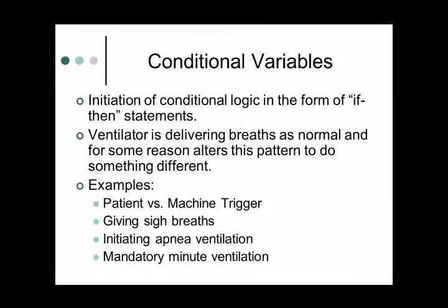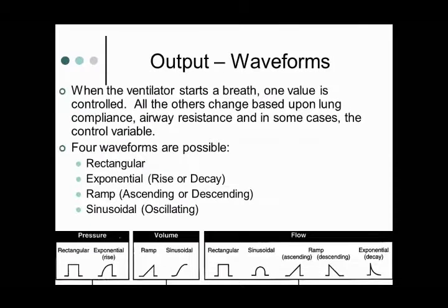If the patient has not triggered and the amount of time between breaths has elapsed, then give a breath. Okay? So they're just conditionals based upon certain situations. And the last part dealing with this is basically that as this ventilator is blowing gas, there is some output that is created, and we can graphically depict that.